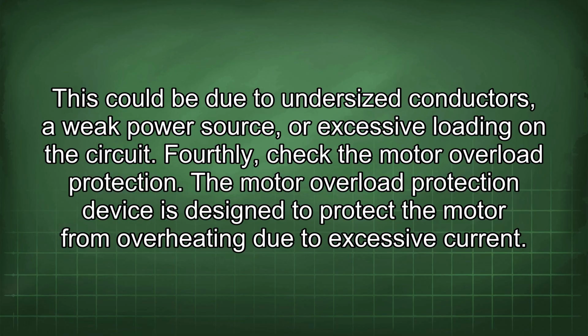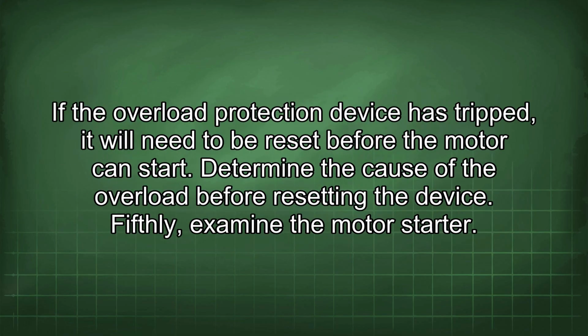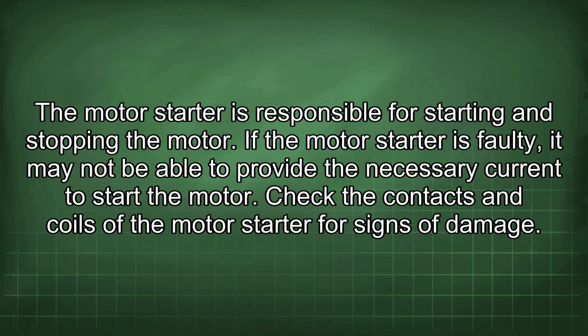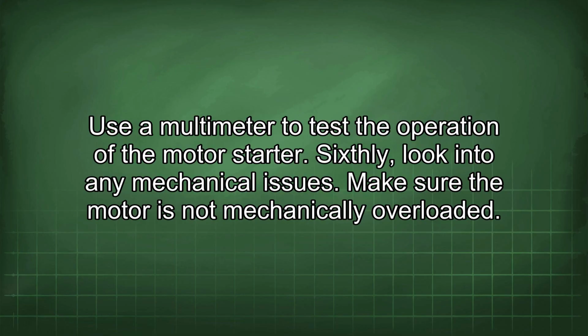Fourthly, check the motor overload protection. The motor overload protection device is designed to protect the motor from overheating due to excessive current. If the overload protection device is tripped, it will need to be reset before the motor can start. Determine the cause of the overload before resetting the device. Fifthly, examine the motor starter. The motor starter is responsible for starting and stopping the motor. If the motor starter is faulty, it may not be able to provide the necessary current to start the motor. Check the contacts and coils of the motor starter for signs of damage. Use a multimeter to test the operation of the motor starter.